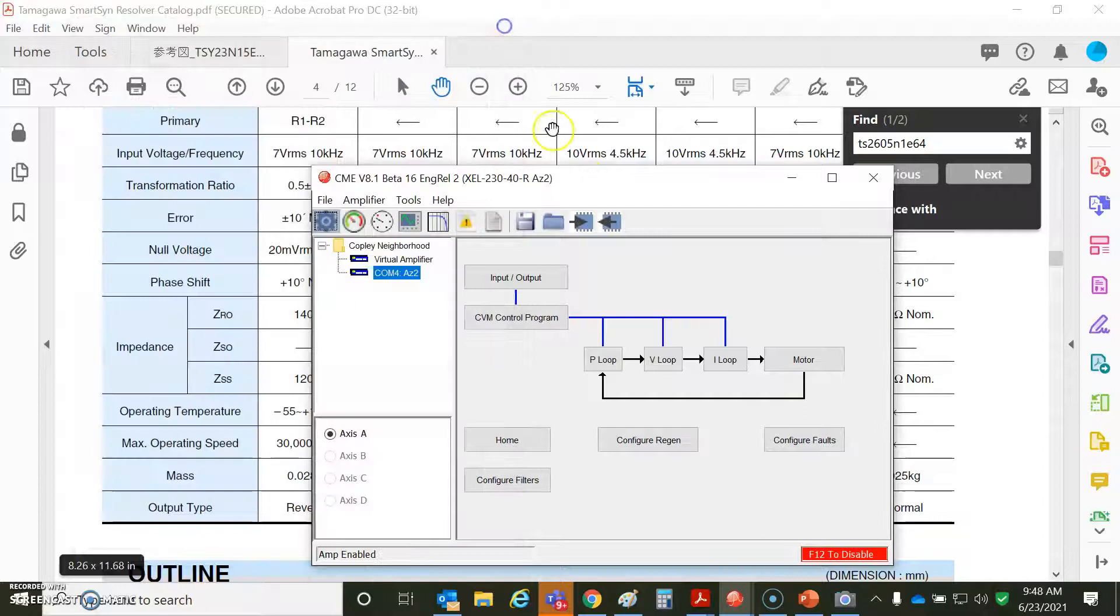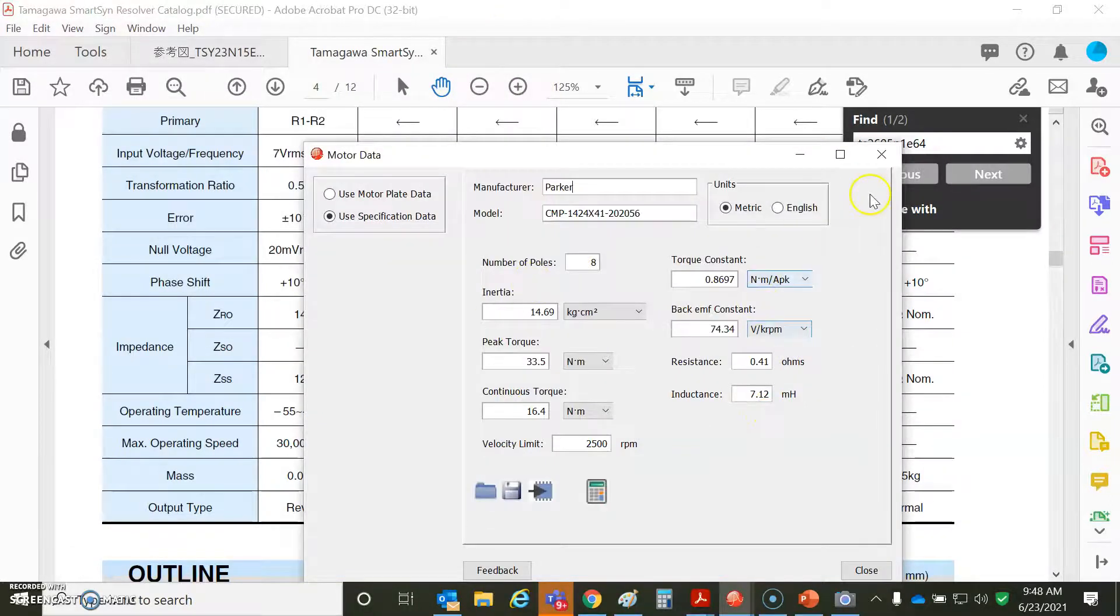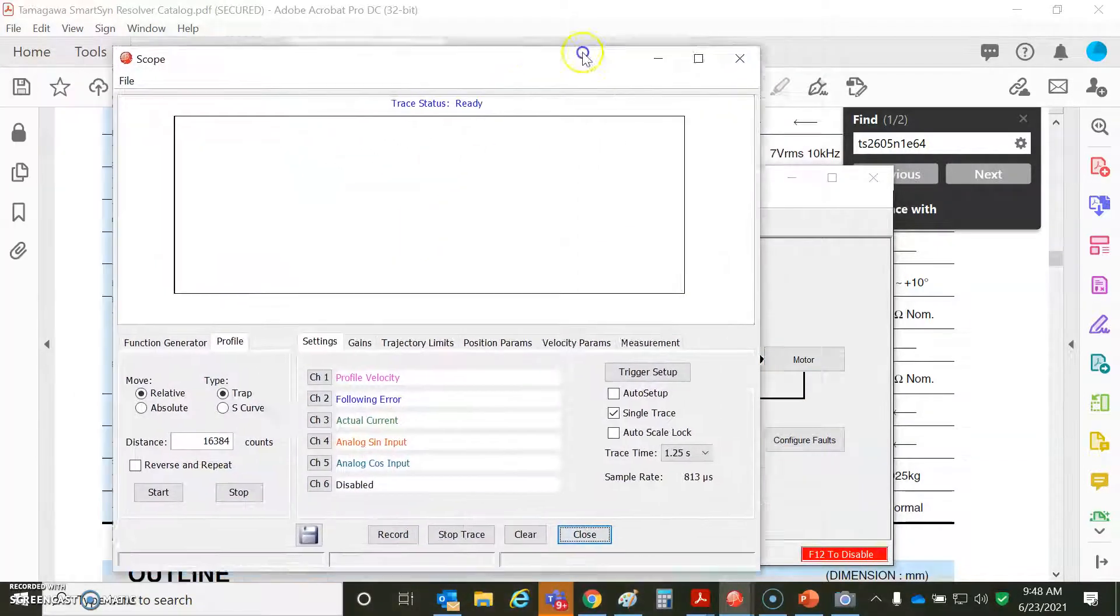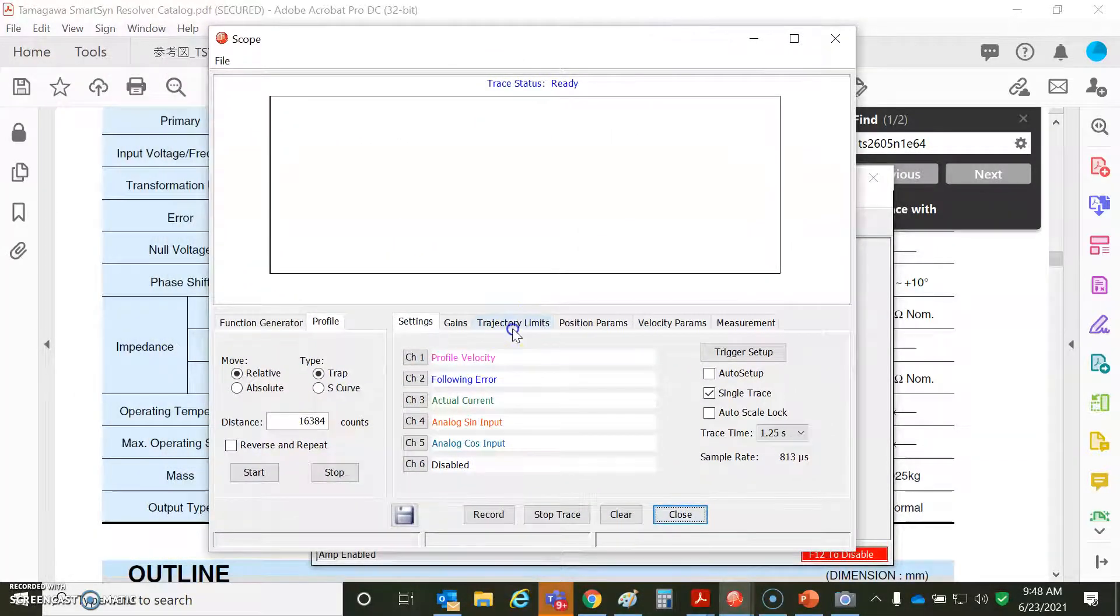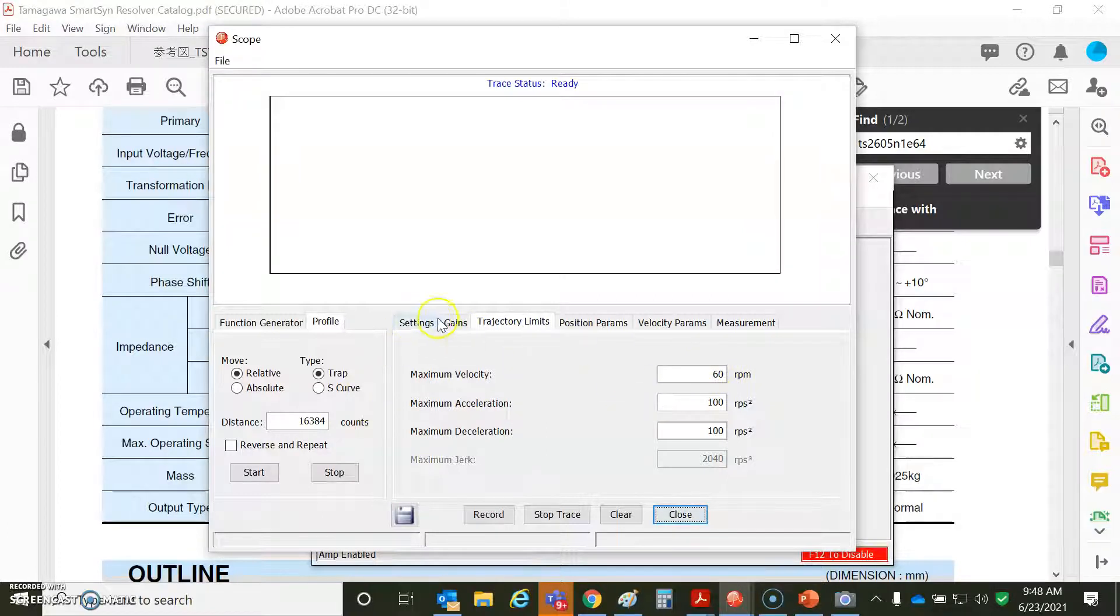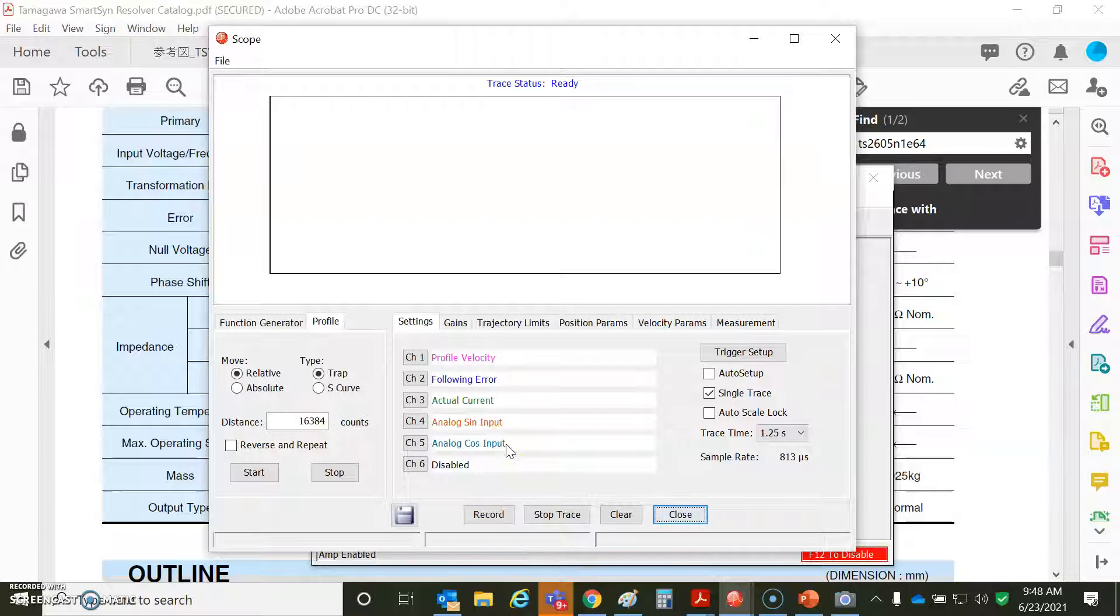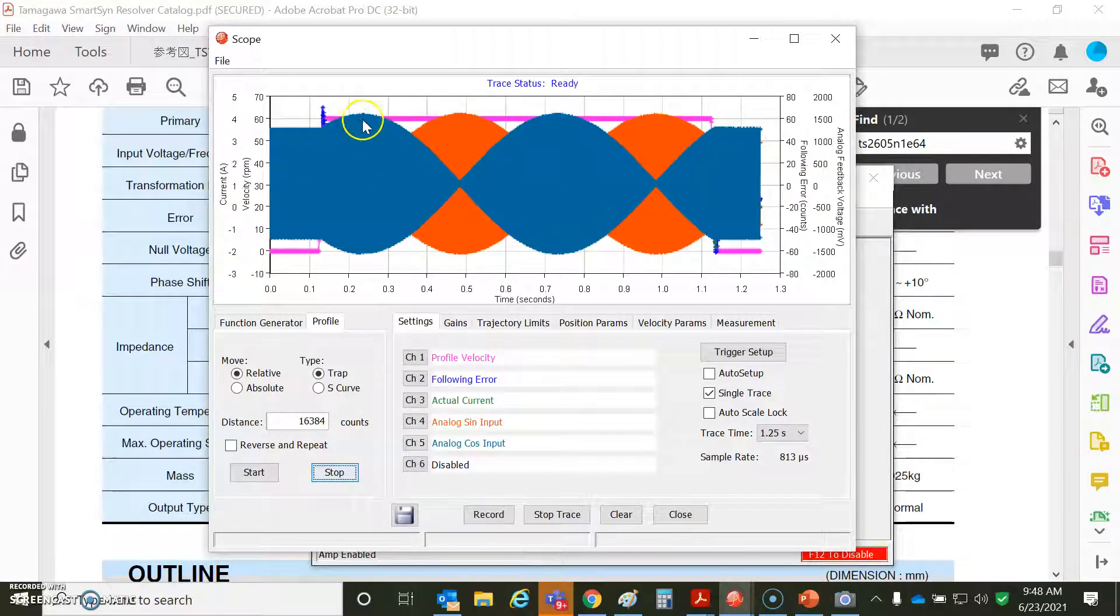You can emulate the output. So resolver in, encoder out. So just got the data for the motor. Did the tuning. So we're going to take a look at doing a single turn rev, 60 RPM profile. So just a one rev move. And I'm going to monitor voltage sine and voltage cosine. Now, you can do this by hand. You can just disable the drive, turn the motor, and watch the sine and cosine coming in. But it's all working now. So I'm going to make a move.